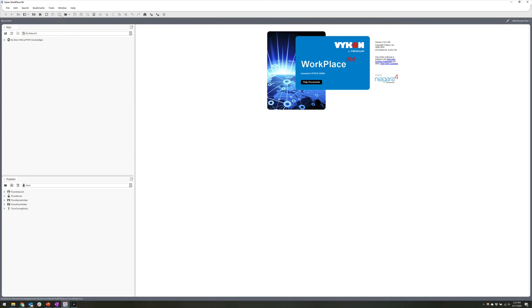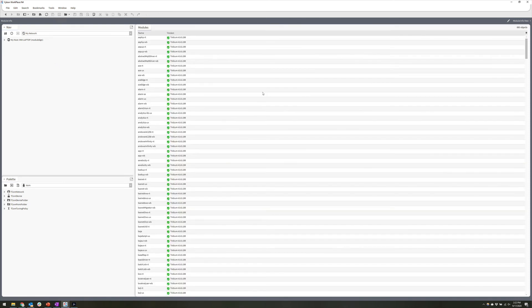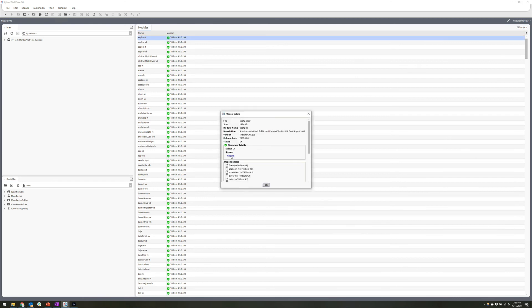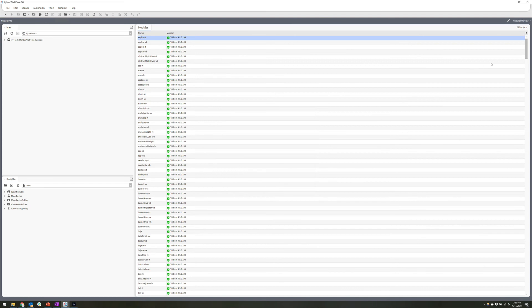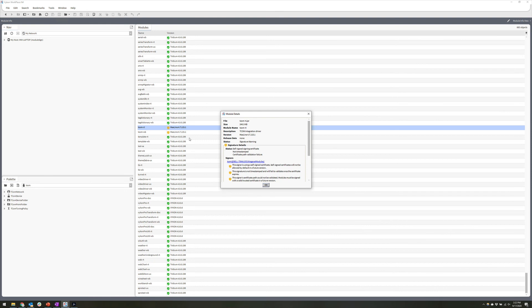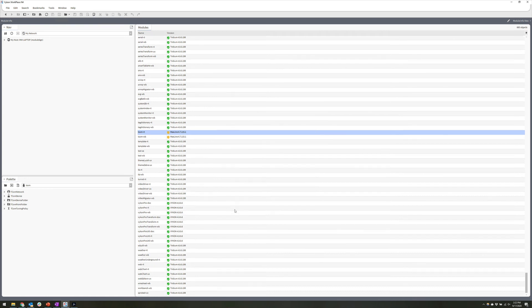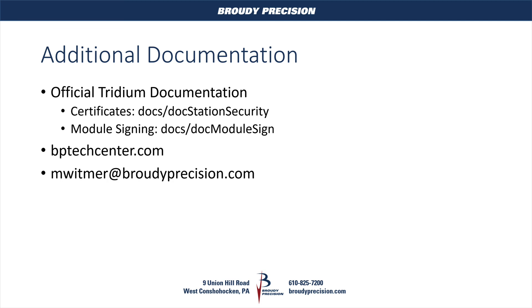A helpful tool you might not have known existed in Niagara: go up to Tools, then Module Info. It will list all the modules you have installed locally on your machine and show you the status of the signature. Opening it up, I can see that a standard module was signed by Niagara — status is okay. But scrolling down to a problem module, you can see these TCOM modules are signed but using a self-signed certificate, which is why I'm getting the yellow exclamation point shield. If a module is not signed at all, you would get a red shield.